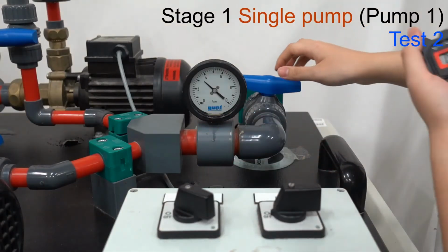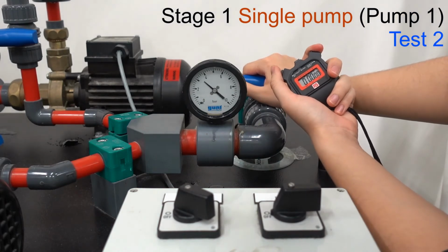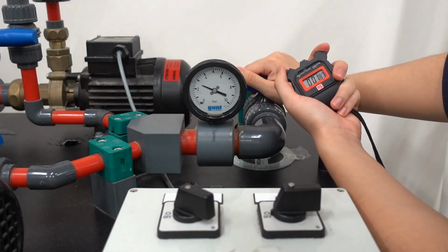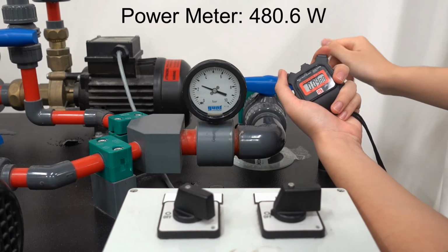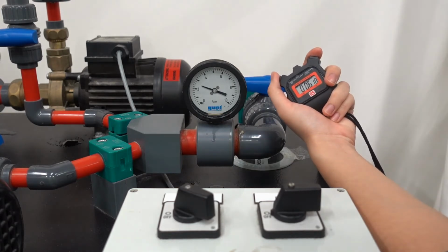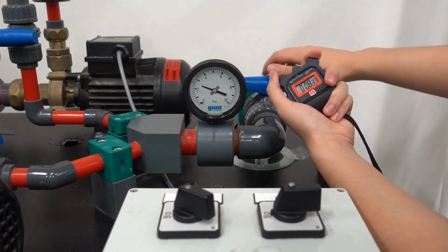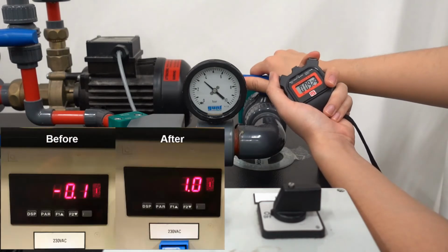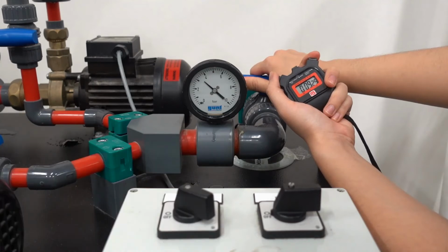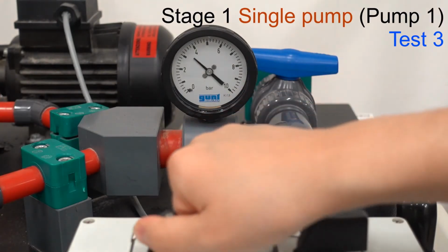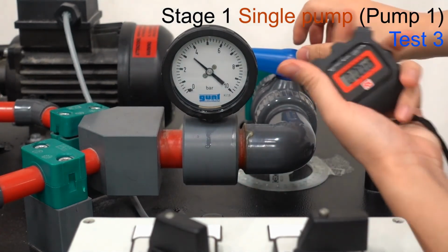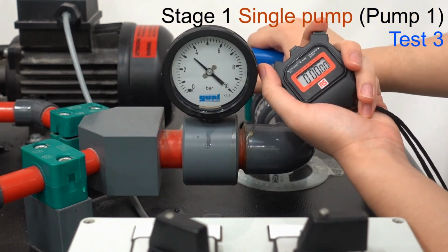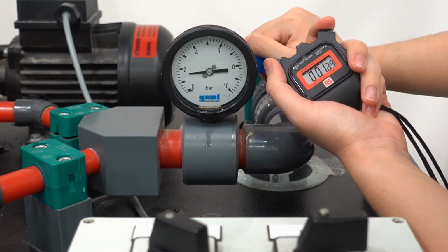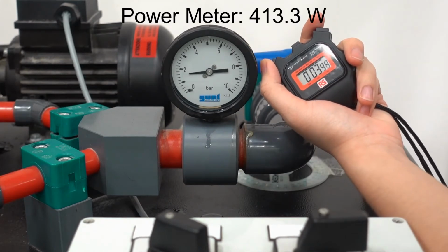For each testing stage, we need to do at least 4 repeating tests to collect enough data for drawing the diagram of characteristic curves. In each repeating test, we will open the valve at a different angle to have a different delivery pressure.